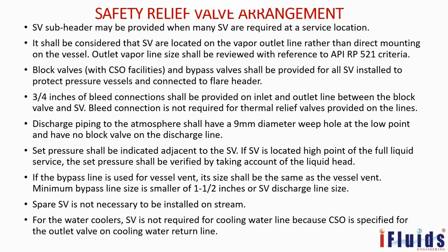If the bypass line is used for vessel vent, its size shall be the same as the vessel vent. Minimum bypass line is the smaller of 1.5 inches or SV discharge line. Spare SV is not necessary to be installed on steam. If PSV SV is installed on a steam pipeline, there is no need of spare.